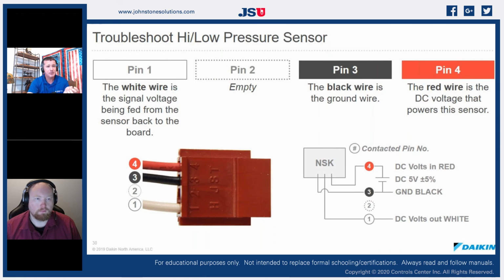When we're talking about those pressure sensors and those transducers, all we are going to do is send our 5-volt DC signal into that sensor, and it's going to change its output based on a change of resistance, right? It's going to change its resistance depending on the pressure or temperature, if it's a temperature sensor. So literally, all we are doing now is taking 5 volts DC, we're going to send in a ground signal with it, we're going to send in 5 volts, and the variable voltage coming back out of that is what is going to run our control board. That's the signal that it needs. So we can check these things either by voltage while it's running, or we can check it by resistance when it's unplugged.